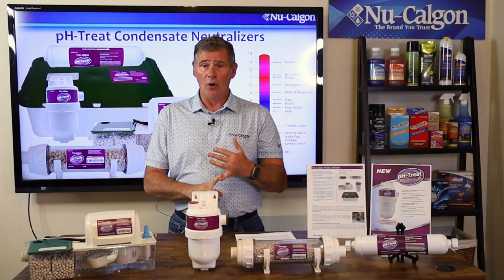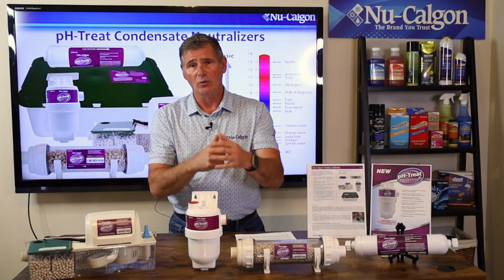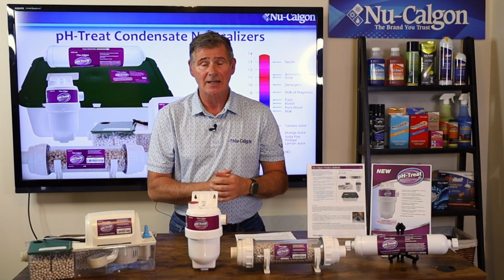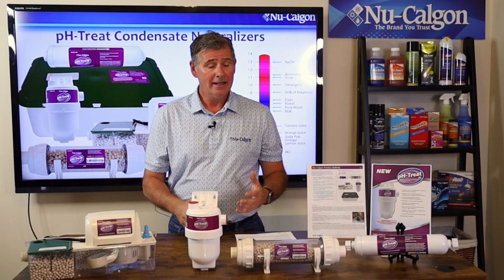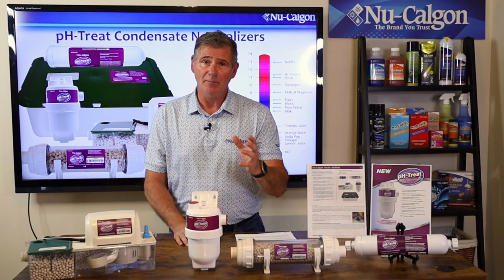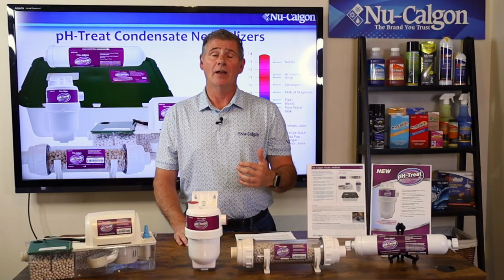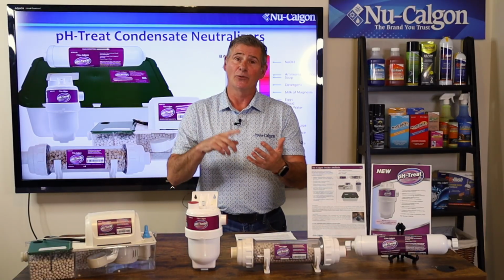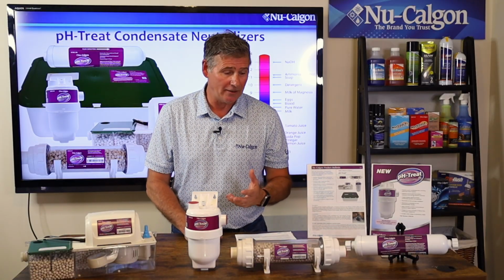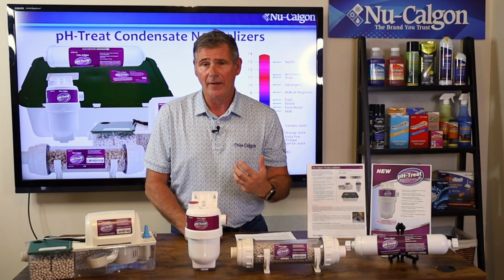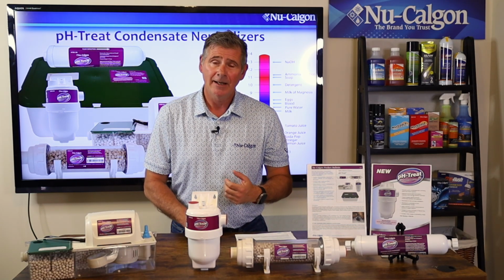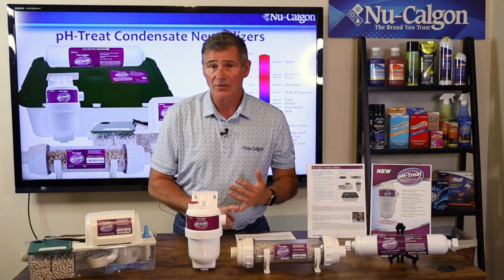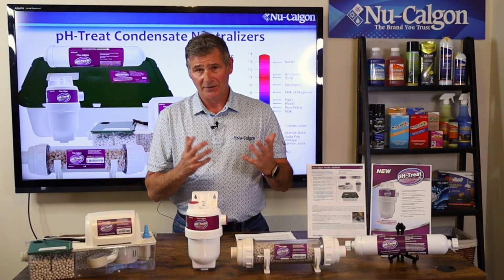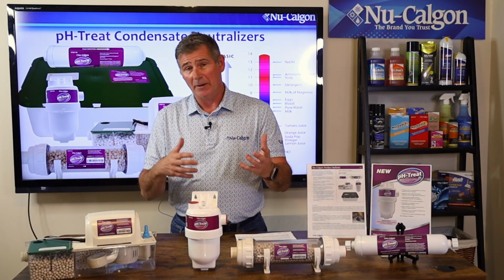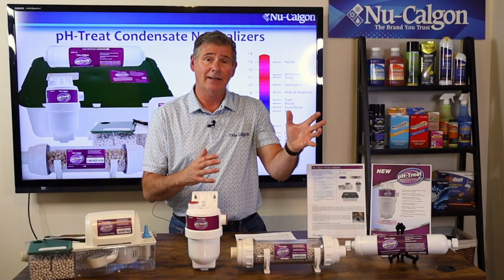Now under certain codes, and you're going to want to check with your local code enforcement, there may be something that requires you to have some type of neutralizing media on the condensate drain lines that come off those high efficiency boilers, furnaces and tankless hot water heaters, because the drain water that comes off them can be very acidic. That acidic water can damage the system that it's coming out of, specifically if you've had some type of blockage and you've got backflow coming back into the system.